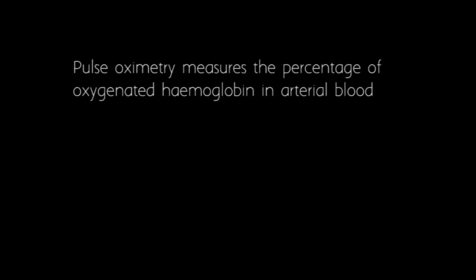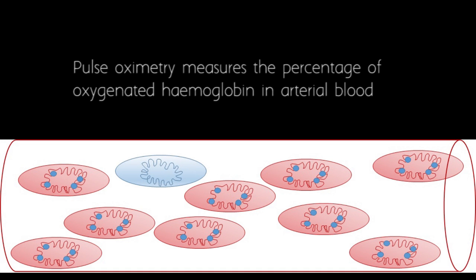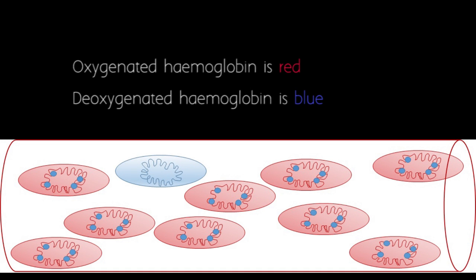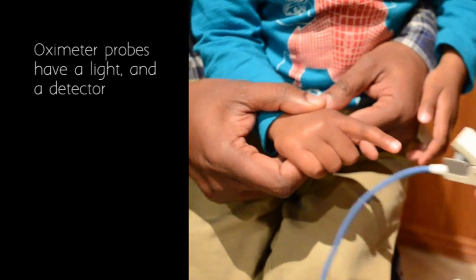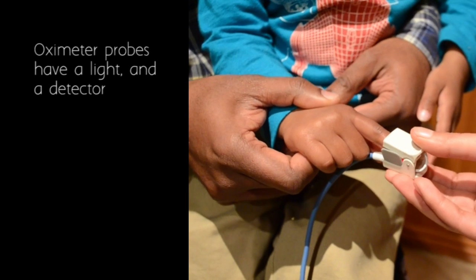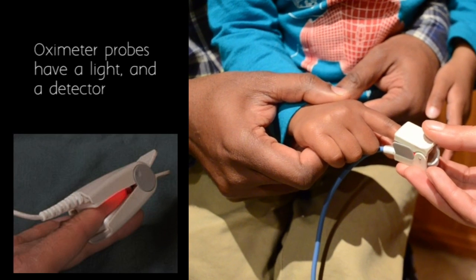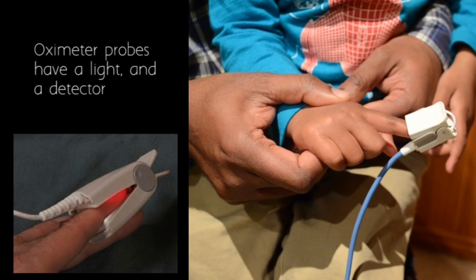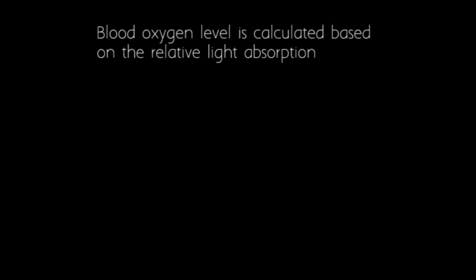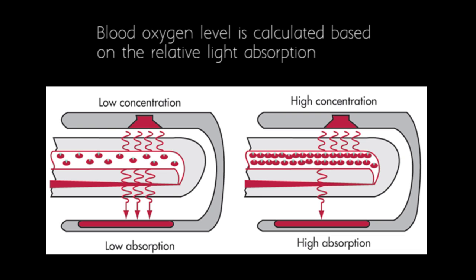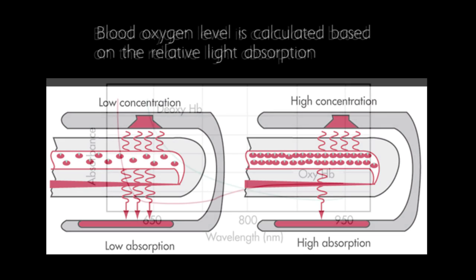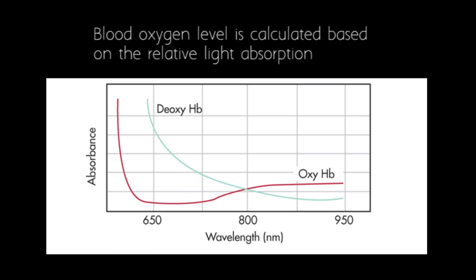Pulse oximetry measures the percentage of oxygenated haemoglobin in arterial blood. Oxygenated haemoglobin is red, while deoxygenated haemoglobin is blue. Inside the oximeter probe is a light which produces red and infrared light when placed on the patient. Opposite the light is a detector. Oxygenated and deoxygenated blood allow different amounts of light through, so the oximeter can calculate the blood oxygen level based on the amount of light transmitted.